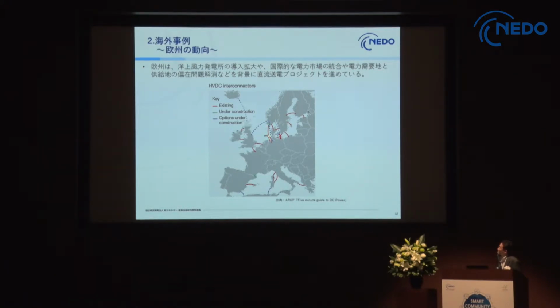So point-to-point, or two-terminal methods, are being used for HVDC interconnections. Two-terminal power transmission is quite simple in terms of current flow, and isolation at the time of an accident is quite easy. However, once an interconnection or transmission line fails, even if the power generator is healthy and intact, the power generated will not be delivered to the consumption market. So there are drawbacks. Especially submarine cables would require much longer time to be repaired, so the damages can be quite significant.